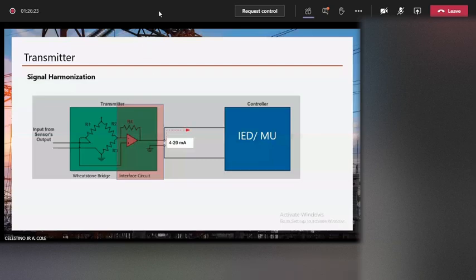Unlike that, if your lowest value is 4, then when it loses supply, it becomes 0, so the system can recognize that as loss of supply. But if the material or medium being measured, like temperature or pressure, goes down to its lowest, the value is still 4. That's the difference between live zero and dead zero.